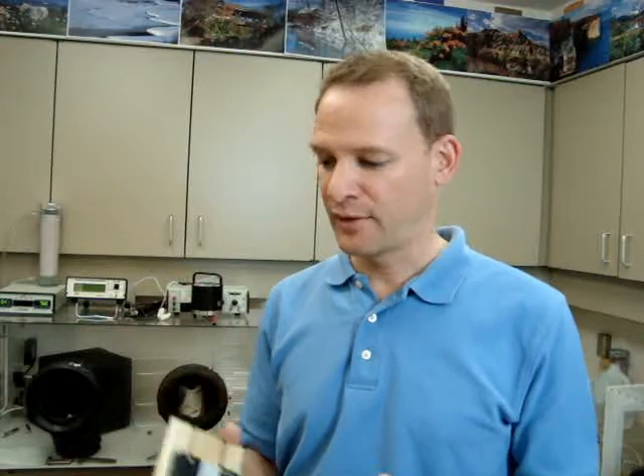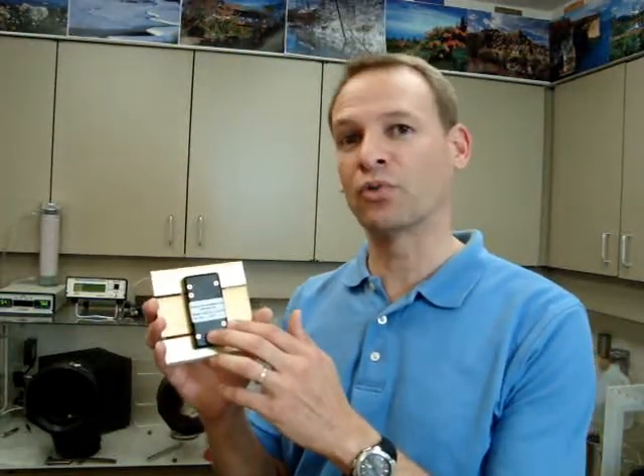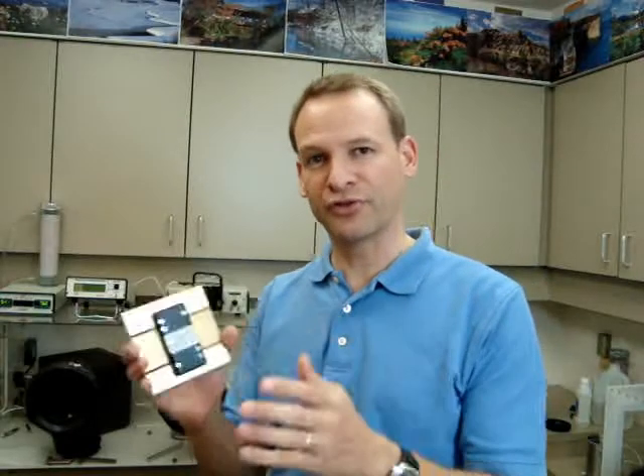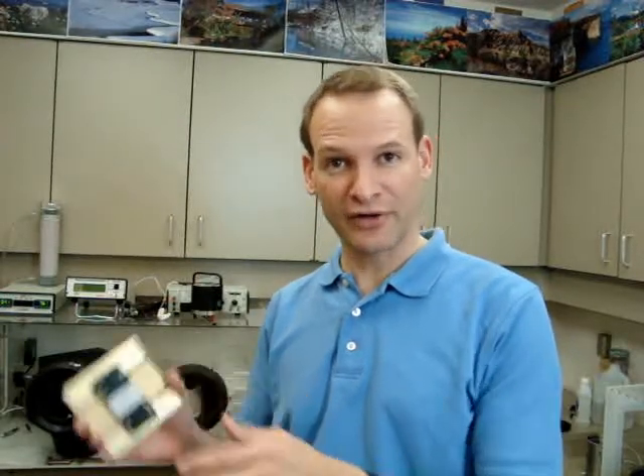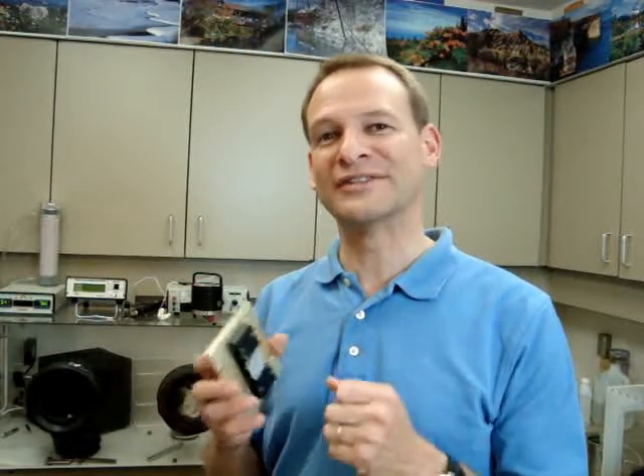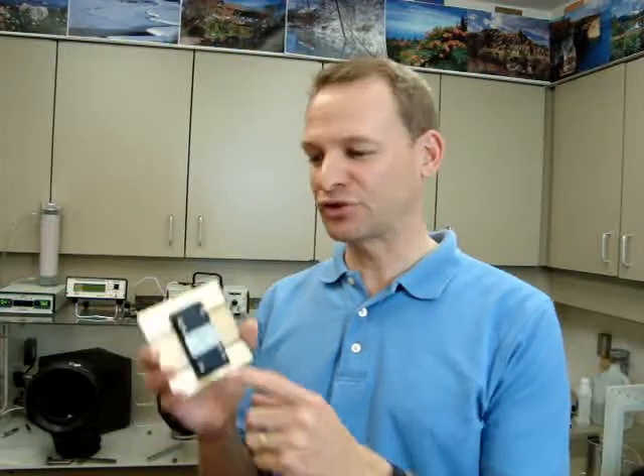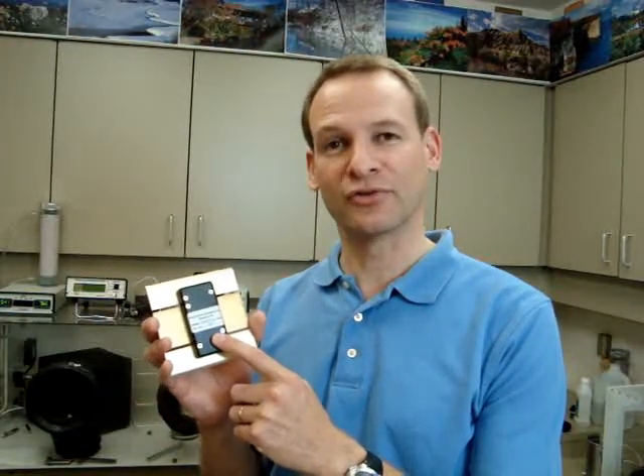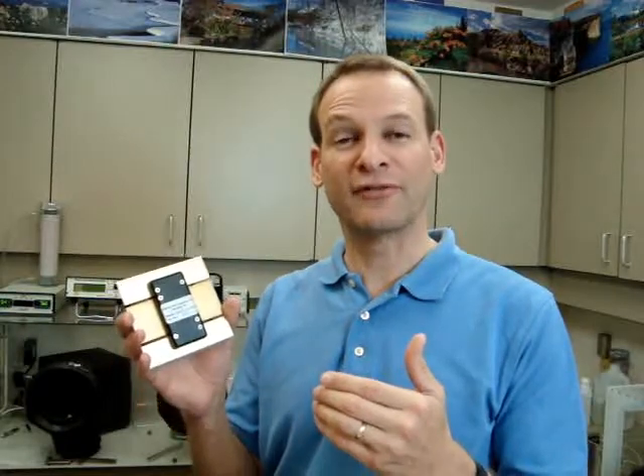So, as an example, the reading stamped on this STM-2 is 0.16 seconds. Now, if you were to put this in your unit and run a test using positive high voltage, and say you get a reading of 0.19 seconds, well, that's good. But now you go to run the test using negative high voltage rather, and you get a reading of 0.16 seconds. Well, even though it's stamped 0.16 seconds on the unit, it failed because the difference between the positive reading and the negative reading is more than 0.02 seconds. So the unit would be out of calibration or out of balance.